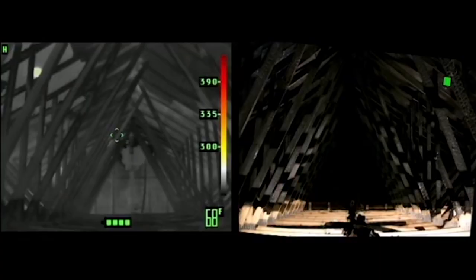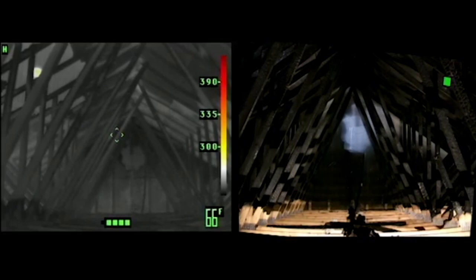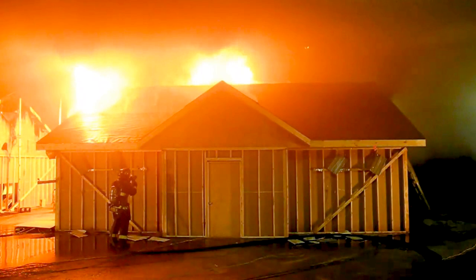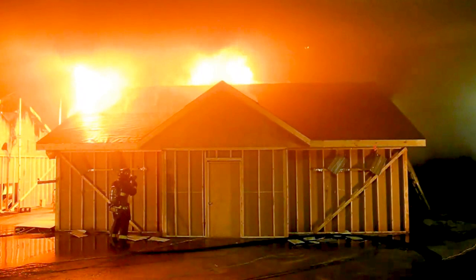Water applied into the eaves can flow along the underside of the sheathing, wetting the surface of the fuel while cooling the space. This can confine and control a fire while maintaining the fire barrier provided by the insulation and drywall ceiling.